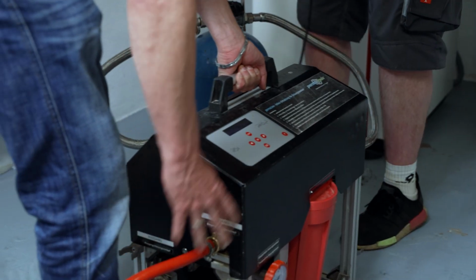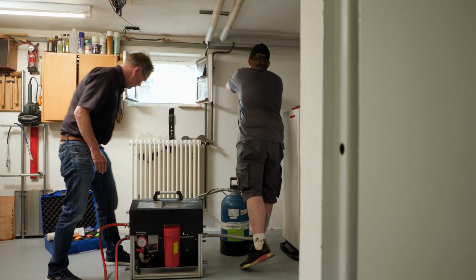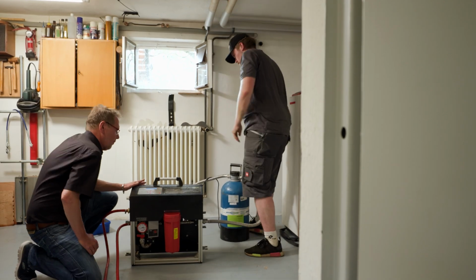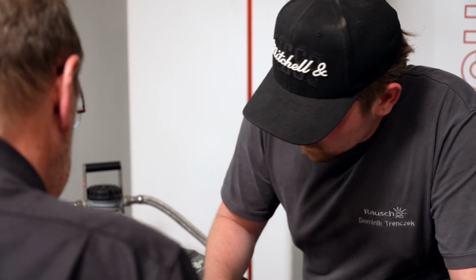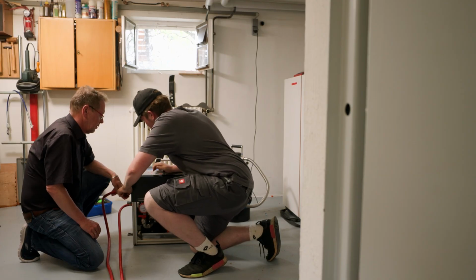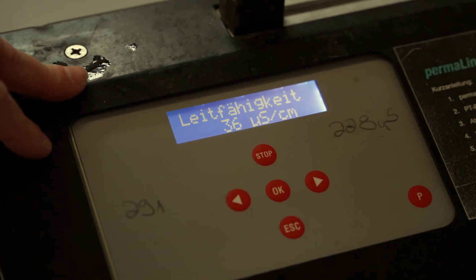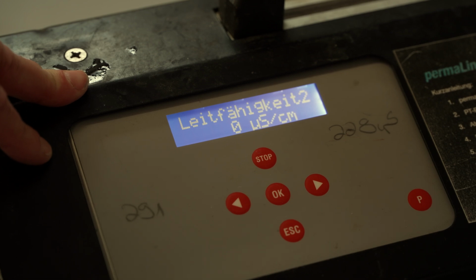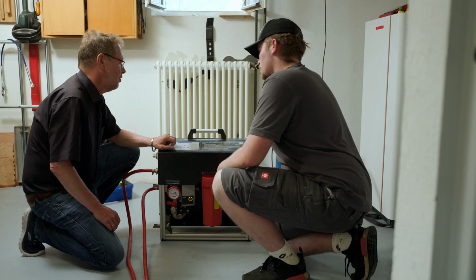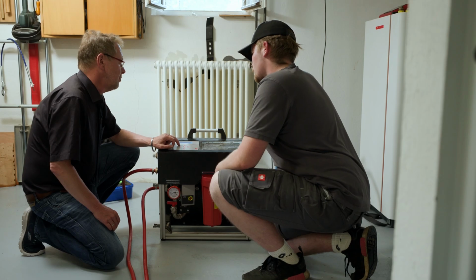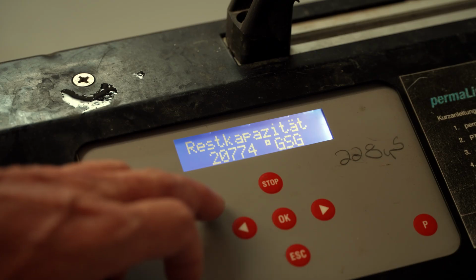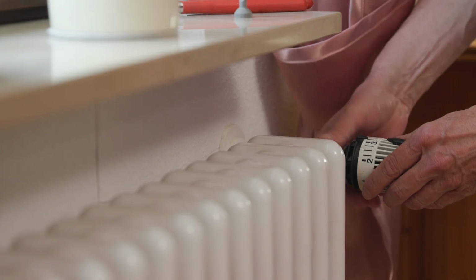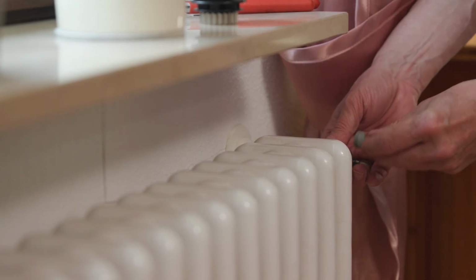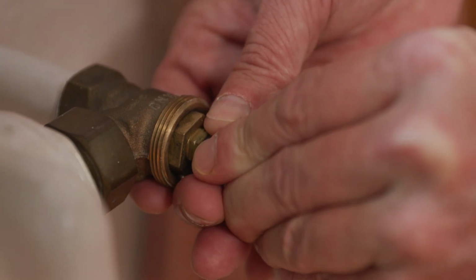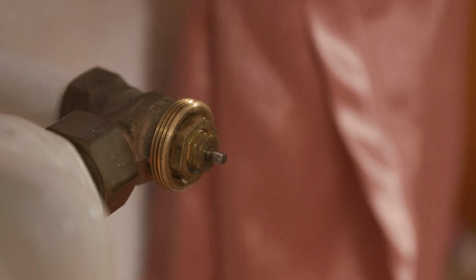Before the heat pump starts operation, the old radiators are flushed clean. During this process, the heating water flows through a filter. This ensures both that no deposits clog the valves and that a defined volume of water flows through the radiators later during operation. Ultimately, the operation of the entire system can continue to be optimized, making it possible to lower the temperature even further. Before the initial startup, a hydraulic calibration is done. This adjusts the flow rate of each radiator and further increases the efficiency of the entire system.